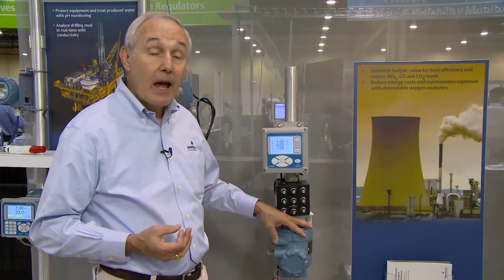So in summary, the 6888 is a flue gas analyzer measuring the remaining oxygen from any combustion process. That can be a large power boiler, an industrial furnace, or a university power plant. It is a no moving parts, low maintenance instrument, and the newest version offers several unique features, including integral AutoCal, safety features for uses in hazardous areas, and plug diffuser diagnostics.